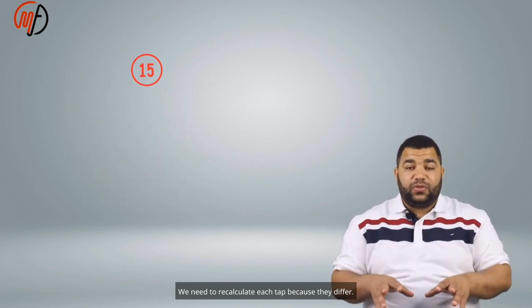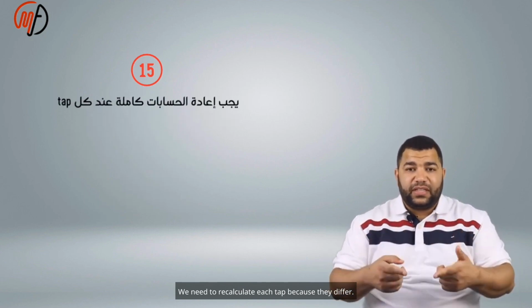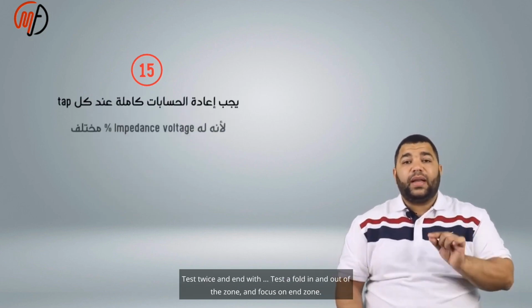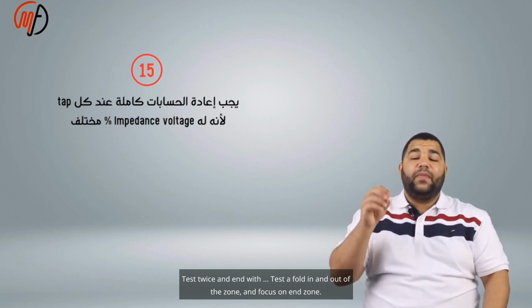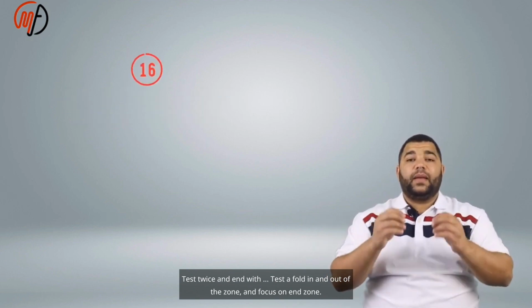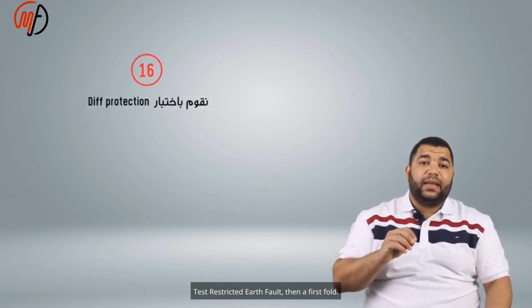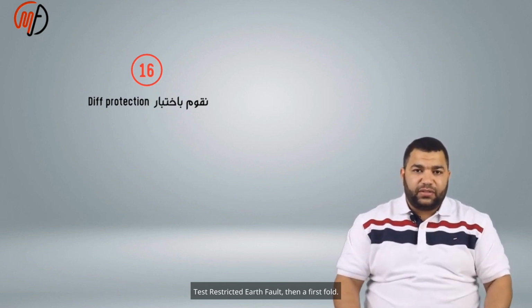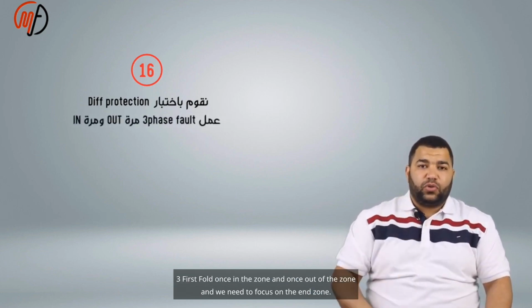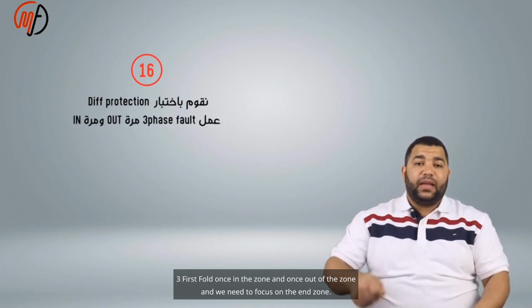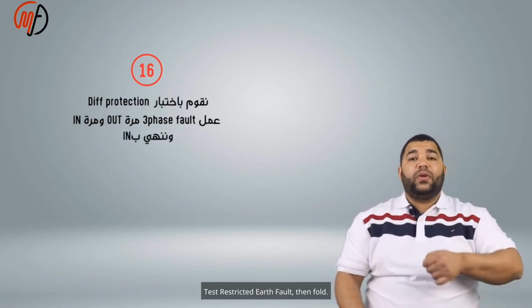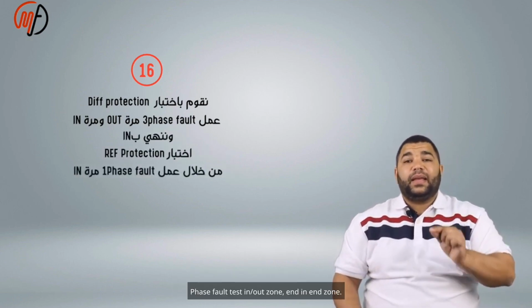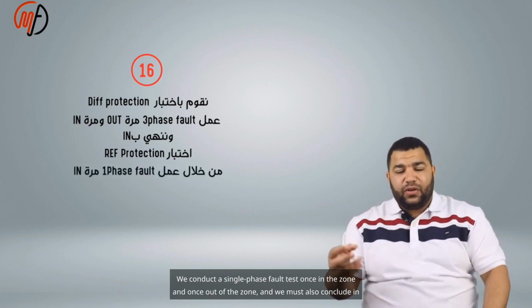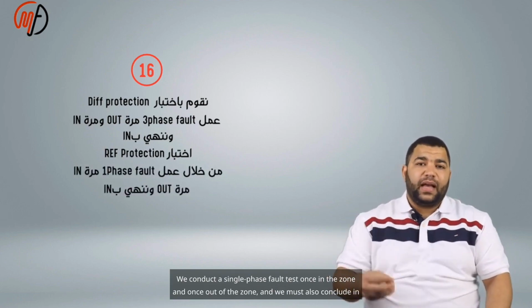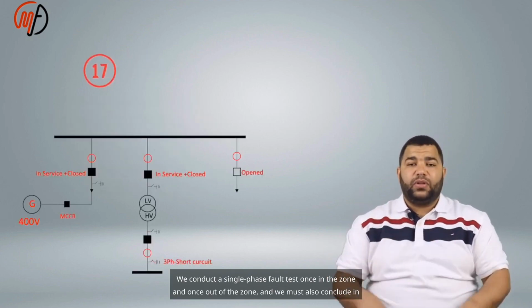We need to recalculate each tap because they differ. Test twice and end with a test in and out of the zone, focusing on the end zone. Test restricted earth fault, then a phase fault test once in the zone and once out of the zone, and we need to focus on the end zone. We conduct a single phase fault test once in the zone and once out of the zone, and we must also conclude in the end zone.